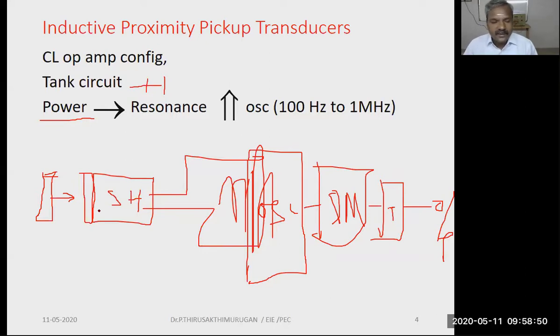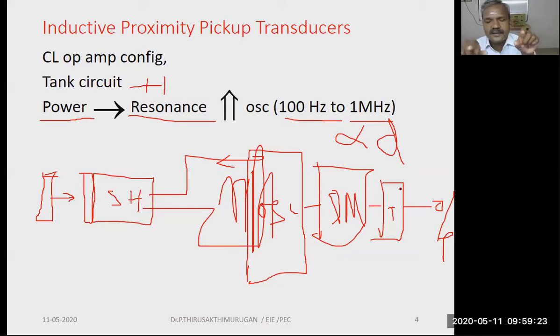So when current generated from the oscillator flows through the sensor head, the resonant frequency is generated. That oscillation frequency ranges from 100 Hz to 1 megahertz. Based on the frequency, we can have the detection of distance, so it is used for the measurement of distance. Normally, the proximity pickup sensors are used as distance measuring devices as well as detectors. The distance measuring range is from 2 mm to 16 mm, only 1.6 centimeter, with high accuracy. That's why we normally use this type of pickup in the field.